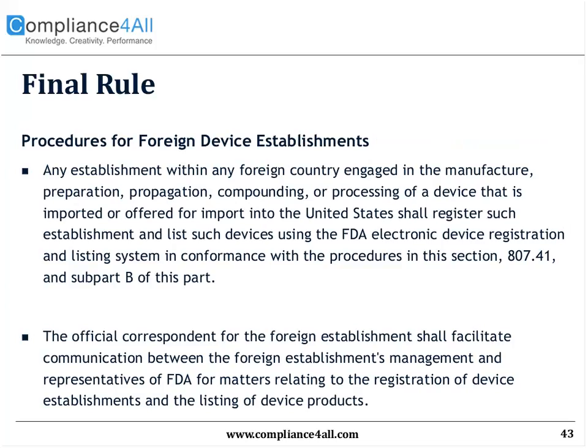If you are online today and you represent a foreign device establishment, a couple things to consider. Any establishment within any foreign country engaged in the manufacture, preparation, propagation, compounding, or processing of a device that is imported or offered for import to the U.S. must, will, and shall register your company and list such device or devices using the same system as we have for domestic manufacturers, that being FDA's Electronic Device Registration and Listing, or the FURLS system. All of this must be done in accordance with 807.41 and Subpart B.